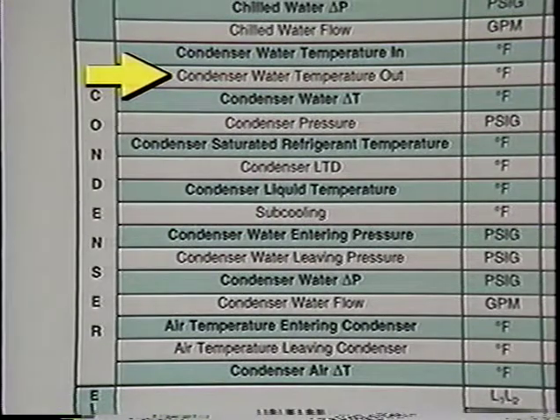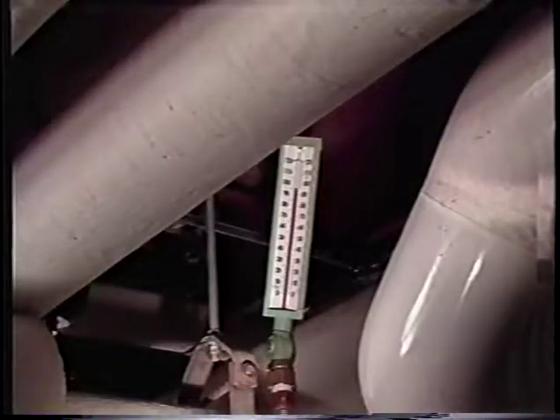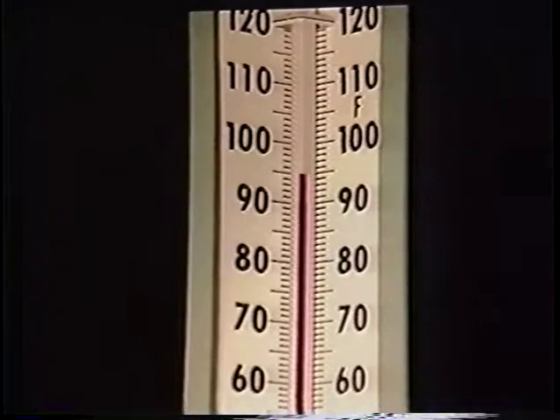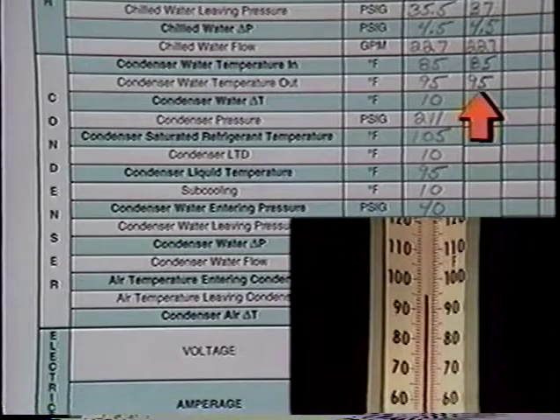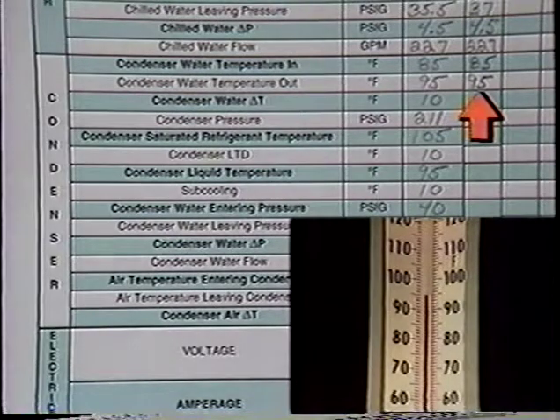Water temperature leaving the condenser. This temperature will vary with the heat load and/or tonnage. Under full heat load conditions, it should not exceed design. Under less than full heat load conditions, the temperature will be less than design.